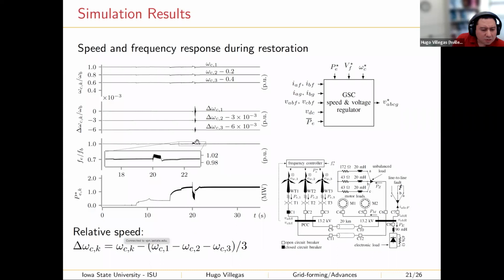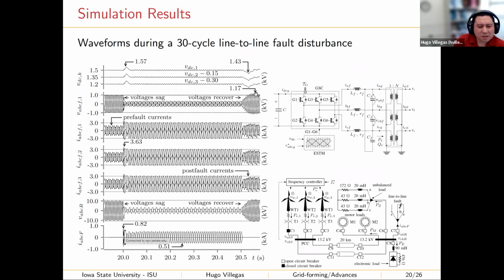During the fault, the frequency also rises a little bit, which is expected because of the amount of electric load that is lost because of the fault. And of course, because the frequency rises, here we have the command from the frequency controller of the wind power plant, which tries to drop the power command of each of the wind turbines because the frequency is going high. And then once the fault is cleared, let's say that C7 opened by some miracle, the system recovers again to a stationary steady state. You can see here the voltage also recovering. There is a slight overvoltage here during the recovery, to 1.17, which is, I think, minor. The current grows a little bit higher than the currents previous to the fault because the motors are recovering speed, so they are withdrawing relatively high reactive currents for the speed recovery.